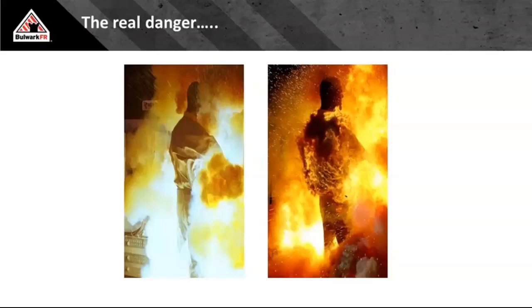0.03 of a second later, literally the blink of an eye, that arc is starting to dissipate. Why? That electrical equipment is designed, when it recognizes a fault, to shut down. And it shuts down relatively quickly. 6 cycles, 4 cycles, whatever the case may be. And cycles are really fast. There's 60 cycles in a second, so a 6-cycle closure is 1/10 of a second. It is shutting down real quick.